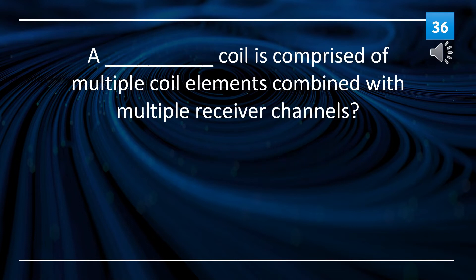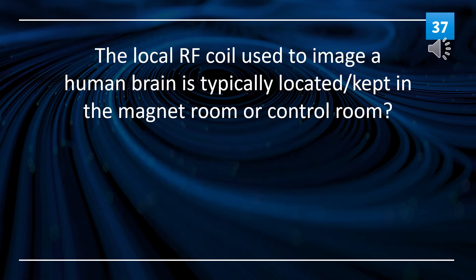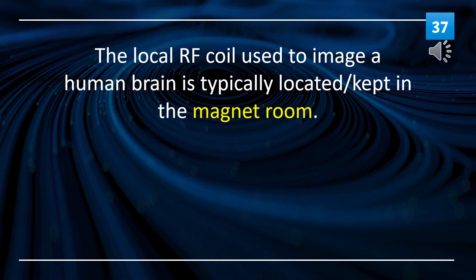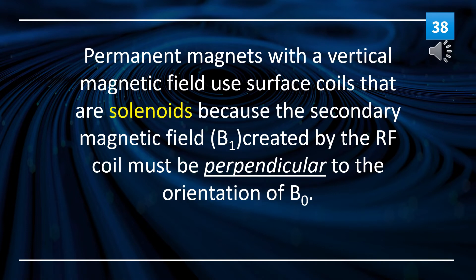A phased array coil is comprised of multiple coil elements combined with multiple receiver channels. The local RF coil used to image a human brain is typically located or kept in the magnet room. Permanent magnets with a vertical magnetic field use surface coils that are solenoids, because the secondary magnetic field B1, created by the RF coil, must be perpendicular to the orientation of B0.